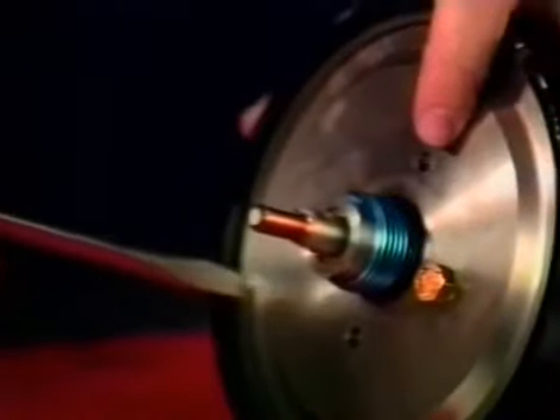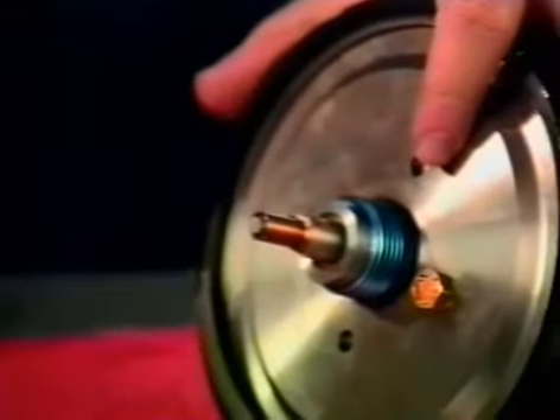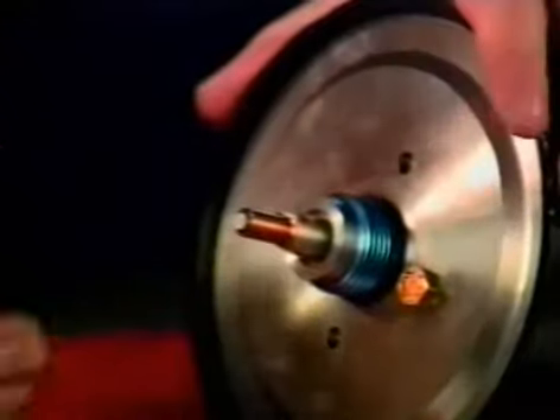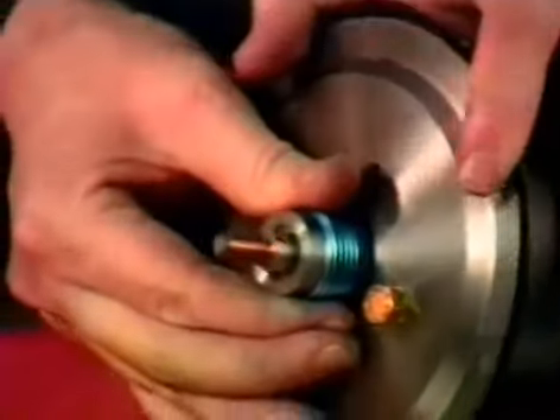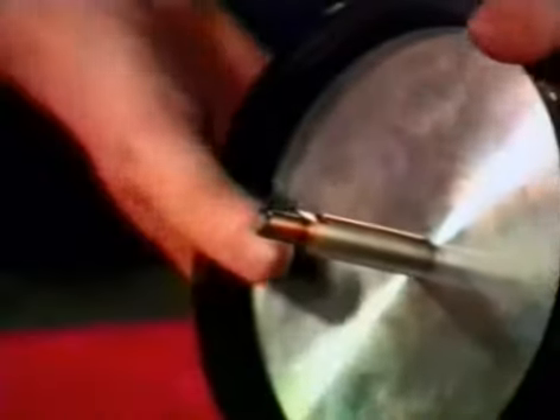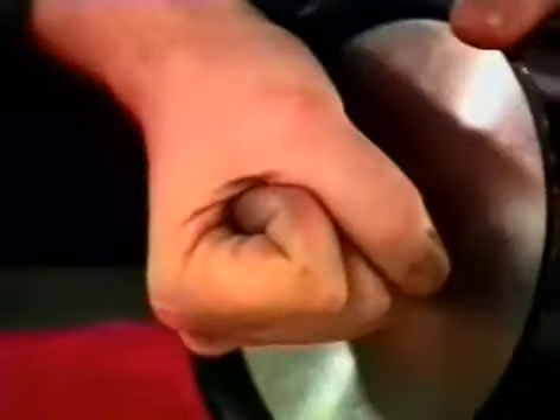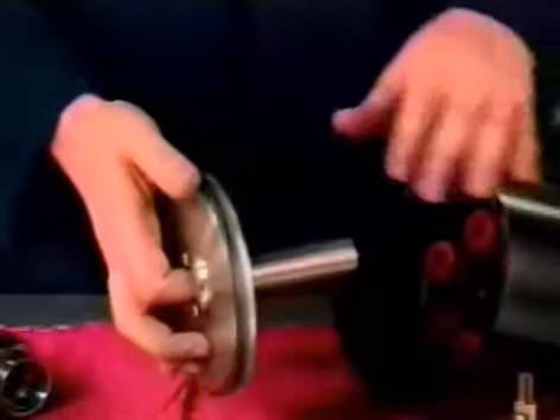To remove the plunger assembly, first remove the retaining ring. Then pull on the plunger assembly. Both the cap and the piston will come out of the valve. Now push on the oil connector to remove the separator plate and the oil connector. Inspect the seals on the piston and separator plate. Replace if needed.